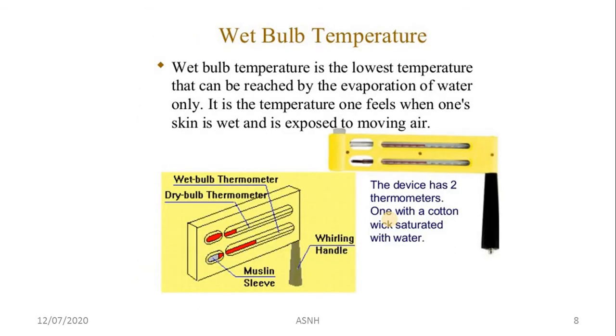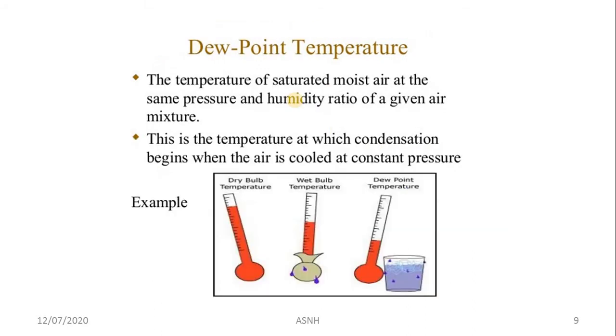Wet bulb temperature is the lowest temperature that can be reached by evaporation of water only. It is the temperature one feels when one's skin is wet and exposed to moving air. A sling psychrometer has two thermometers: the dry bulb thermometer's bulb is not covered, while the wet bulb thermometer's bulb is covered by a wet cloth.